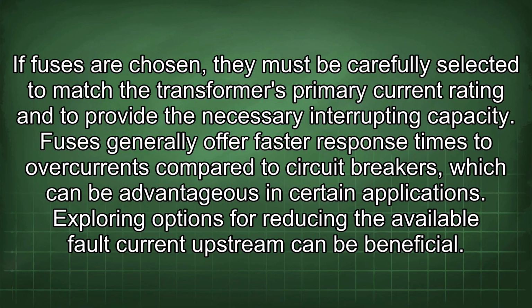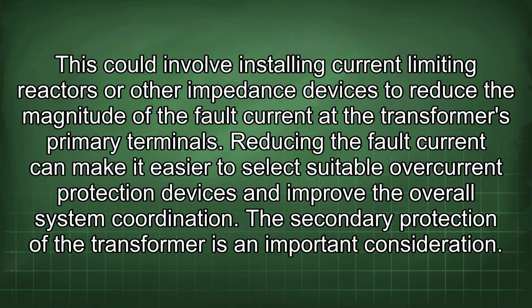Exploring options for reducing the available fault current upstream can be beneficial. This could involve installing current-limiting reactors or other impedance devices to reduce the magnitude of the fault current at the transformer's primary terminals. Reducing the fault current can make it easier to select suitable overcurrent protection devices and improve the overall system coordination. The secondary protection of the transformer is an important consideration.